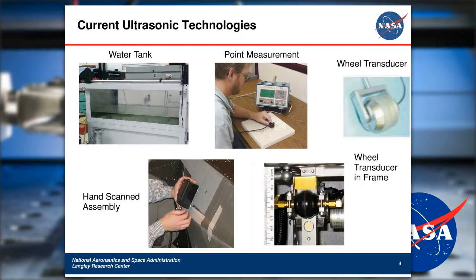In the lower left image you have a hand scan assembly, which is an ultrasonic wheel transducer and a frame. It can only go in one direction, and you can see in that lower left image there are some vertical lines drawn, so the inspector will push that assembly, following that vertical line, to build up the inspection image.